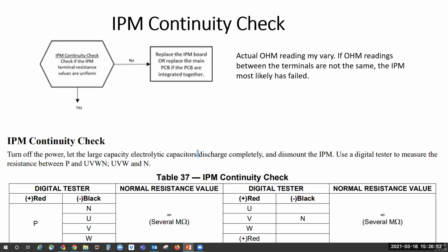We're checking for resistance when we get to this board. We're not looking for any set resistance, just a consistent resistance. You put your red lead on the P and move the black one between the U, V, and the W, and they need to be very close to the same. If you don't get anything, it's possible you don't have a good connection. I always recommend doing this at least twice, maybe 3 times, depending on how much coating they've put over it.